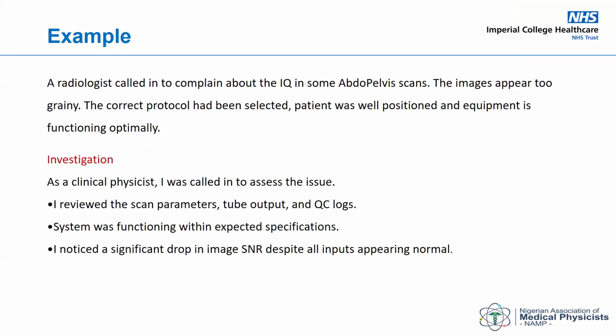So for investigation purposes, you want to ensure that the scan parameters are correct. How do you know? Because you have a protocol. As a physicist, you must have a copy of all of the protocols that you use in your facility, whether for chest, for head, for neck, for shoulder, for knee, for foot. And you want to compare that every time there's an issue. You want to be sure the scan parameters are correct. The right KV has been selected. The right protocol has been selected. The right filtration has been used. Tube output and QC logs have not flagged anything. System was functioning within expected specification.